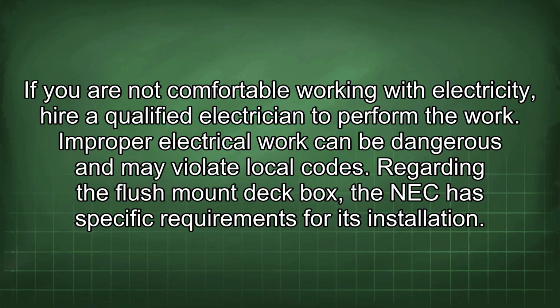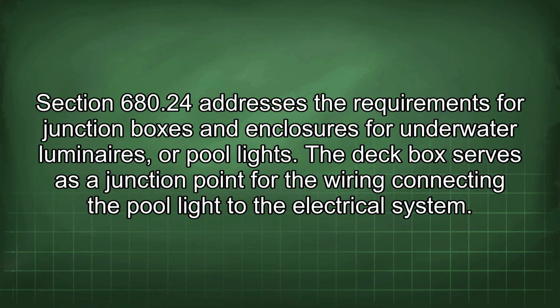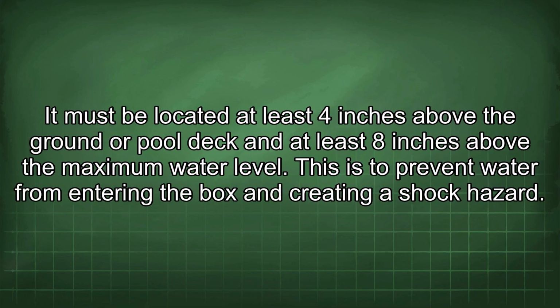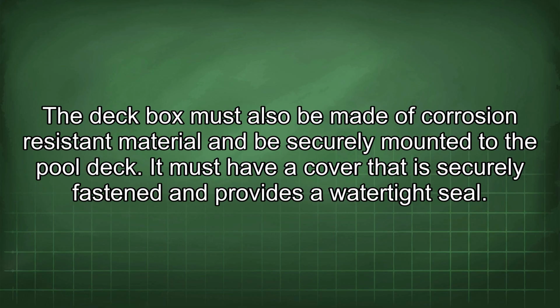Regarding the flush mount deck box, the NEC has specific requirements for its installation. Section 680.24 addresses the requirements for junction boxes and enclosures for underwater luminaires or pool lights. The deck box serves as a junction point for the wiring connecting the pool light to the electrical system. It must be located at least 4 inches above the ground or pool deck and at least 8 inches above the maximum water level. This is to prevent water from entering the box and creating a shock hazard. The deck box must also be made of corrosion-resistant material and be securely mounted to the pool deck. It must have a cover that is securely fastened and provides a watertight seal.